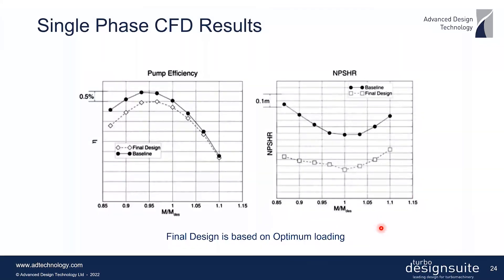The single-phase CFD results show that with this new design there is only a small drop in efficiency — less than half a percent at the design flow rate — while also achieving a very good improvement in NPSHR.